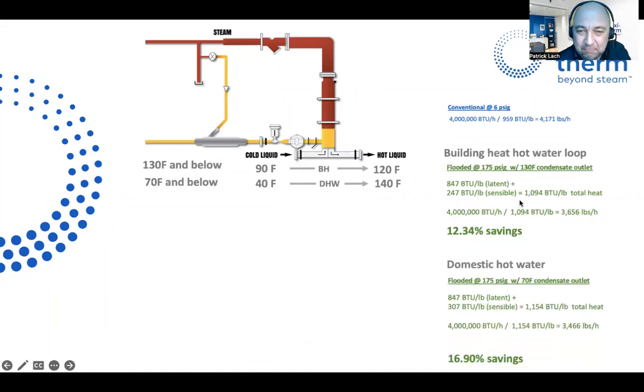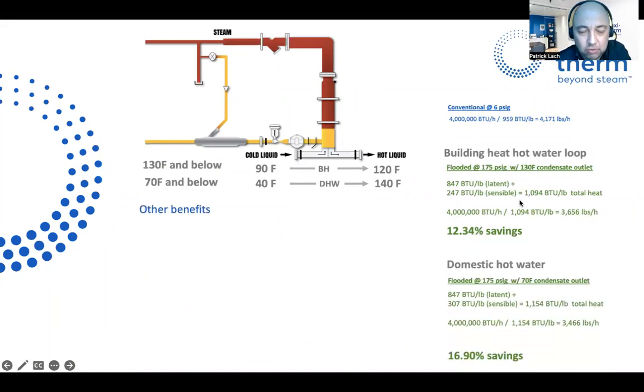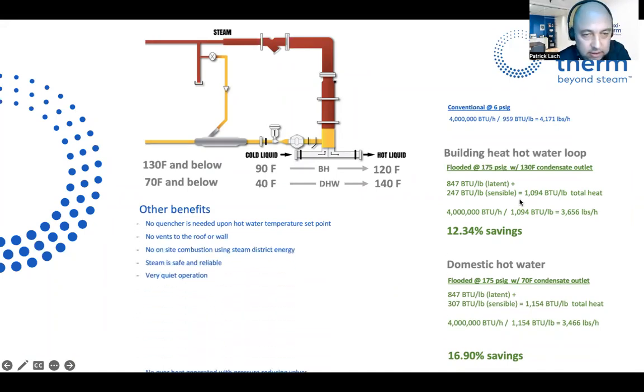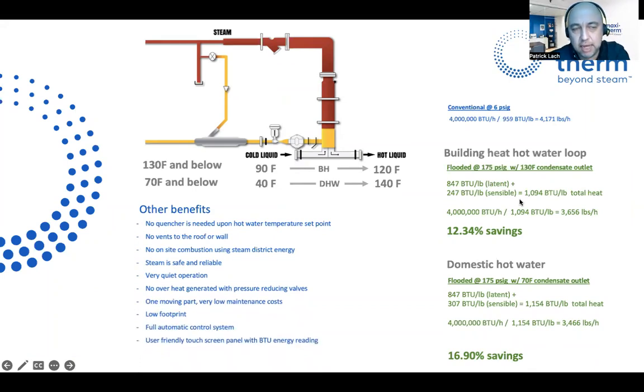Sorry for that. So there are two different options that we see in buildings, hospitals, universities, or factories. The number one application we do the most is BH, what's called building heat. So a hydronic closed loop, hot water loop. Let's say we're controlling a 120 Fahrenheit set point with a potential return at 90. That means condensate can leave at 130. In example number two, domestic hot water, 40 to 140, and condensate can leave at 70 Fahrenheit.